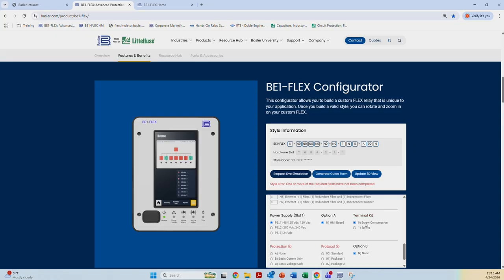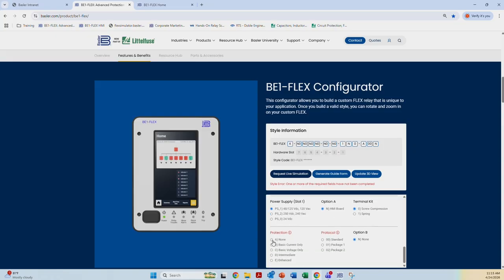The screw compression terminal kits are for the power supply and digital inputs. The analog connections are ring tongue connections. Then I would select the protection package. For this particular application, as we reviewed earlier, we would need some voltage protection and overcurrent protection. If you're unsure of what protection elements are included in what package, you can select the information button, and it tells you what protection elements are available in what protection packages. So for this particular application, it looks like you need the intermediate because we need basic voltage and basic current both.